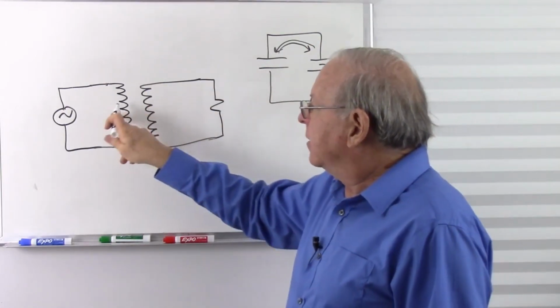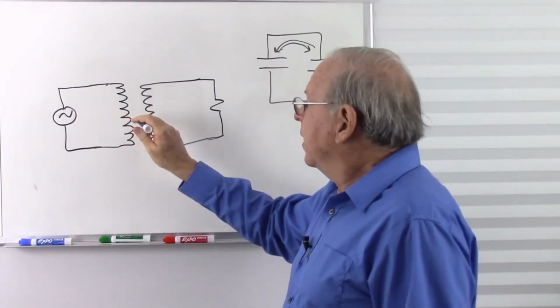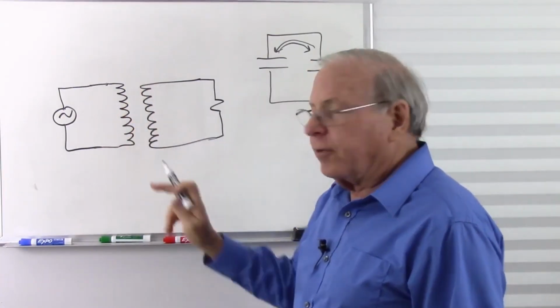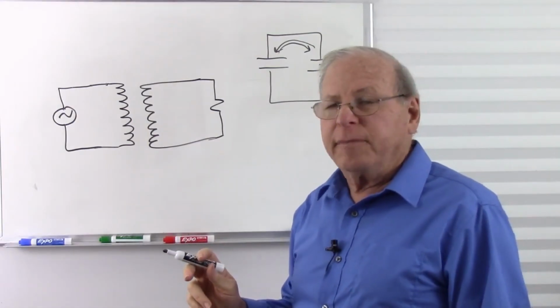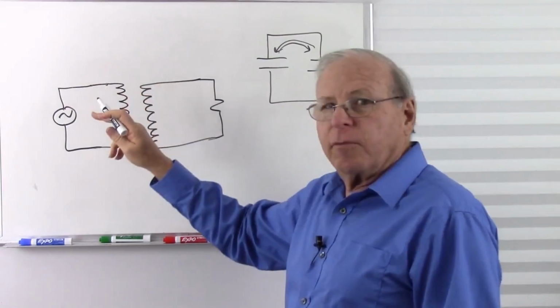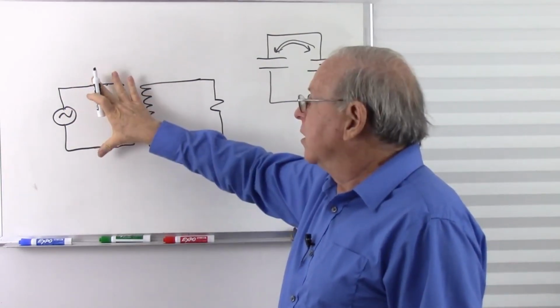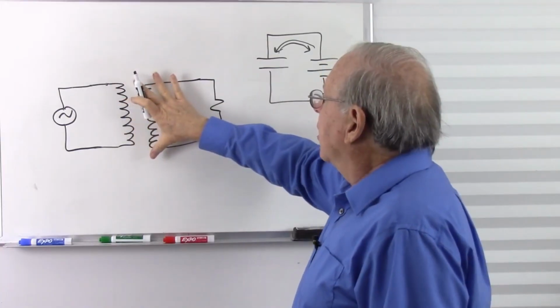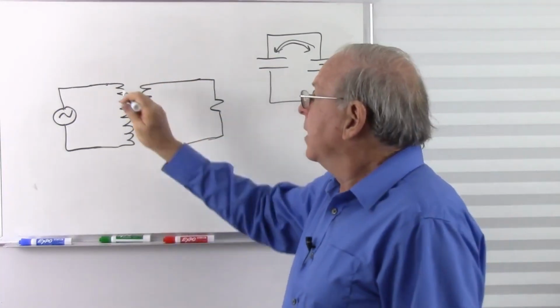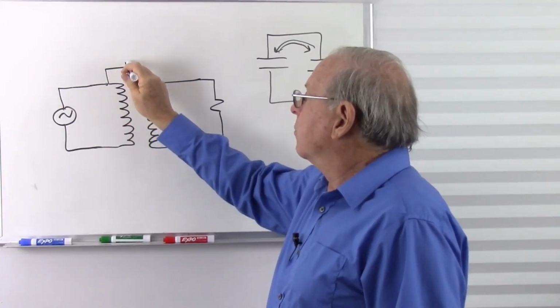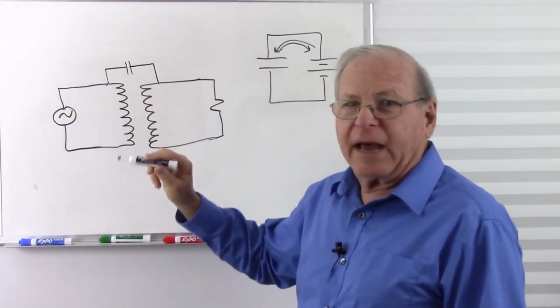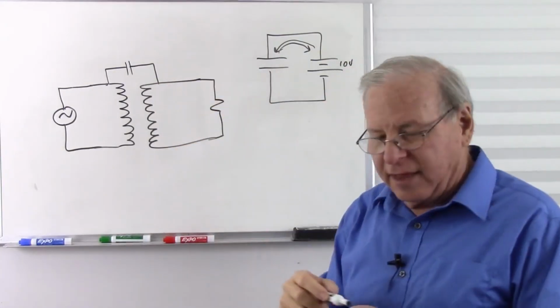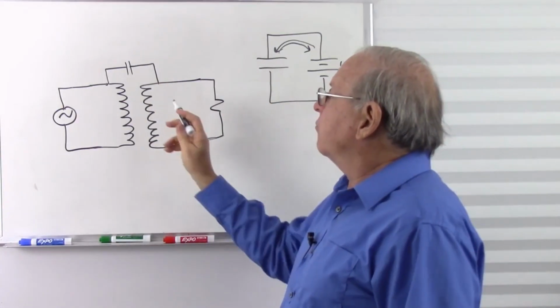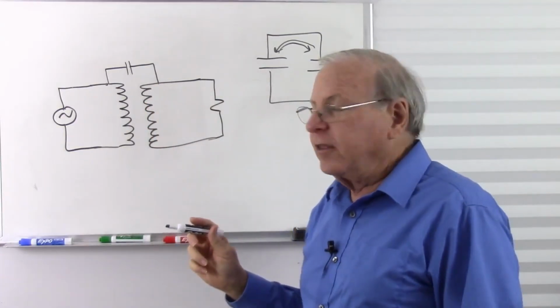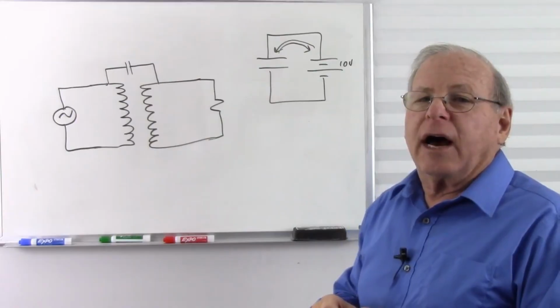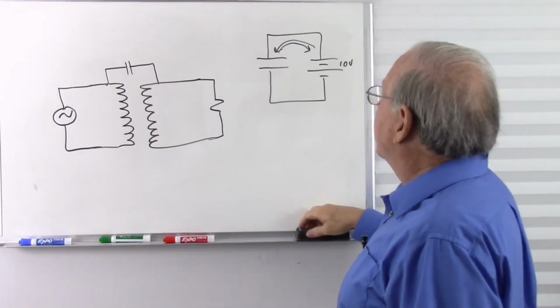Well, what do we have here at the transformer? We have two conductors separated by an insulation. Looks like a capacitor to me. Can we get capacitive coupling from one side to the other? As current goes in, do we get a charge and it causes current to flow in the other side? You bet it does. So an engineering model of a transformer will put a capacitor here. That's not a real capacitor, it's just representing the natural capacitance that we have in the transformer. And that illustrates that we do have capacitive coupling from one side to the other. So when we make an isolation transformer, we want to minimize that capacitive coupling.